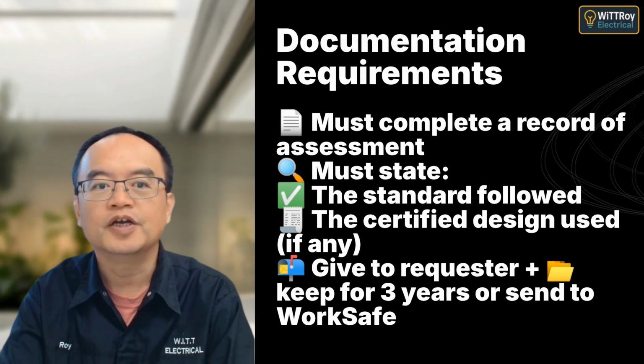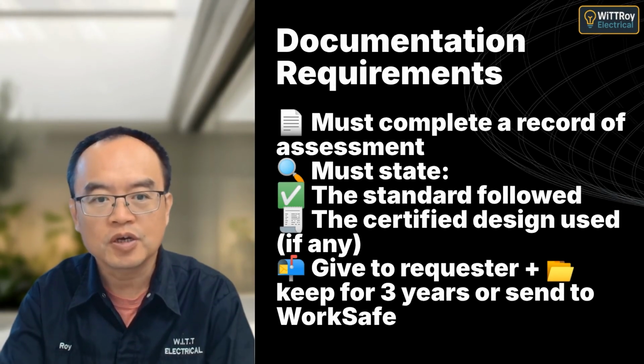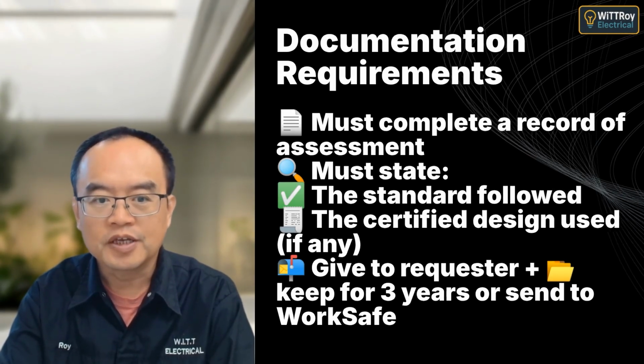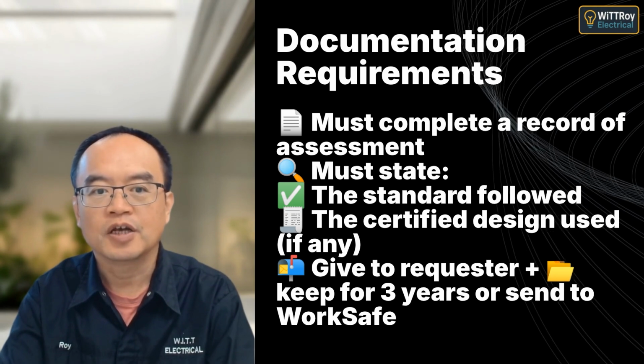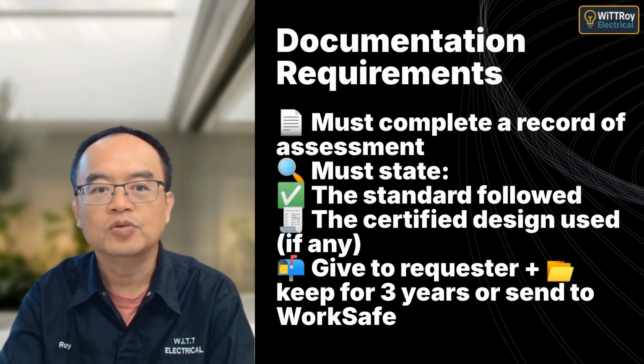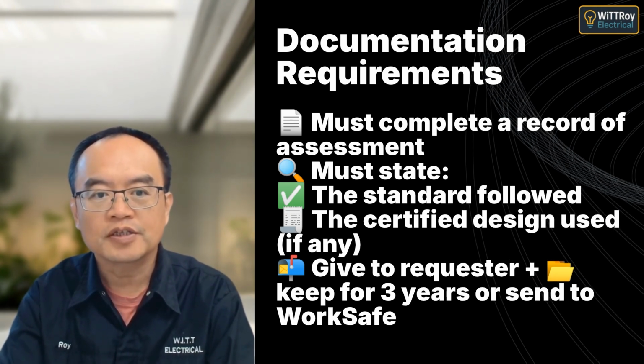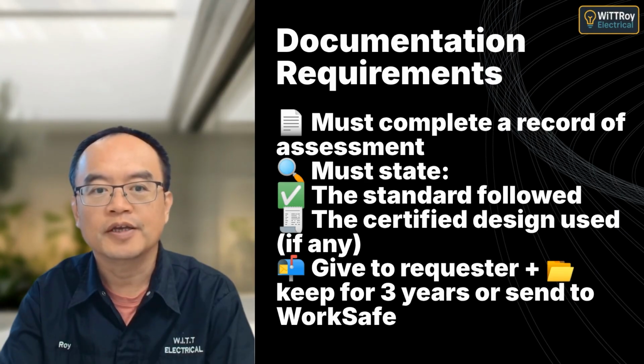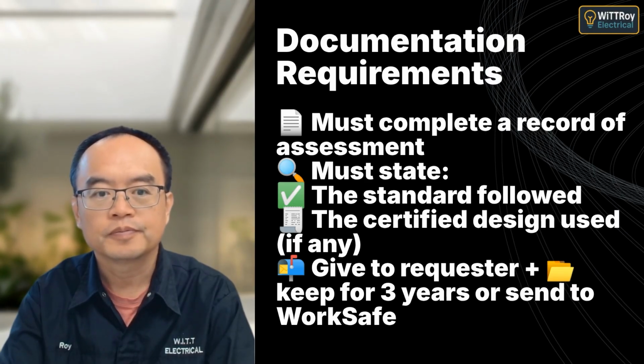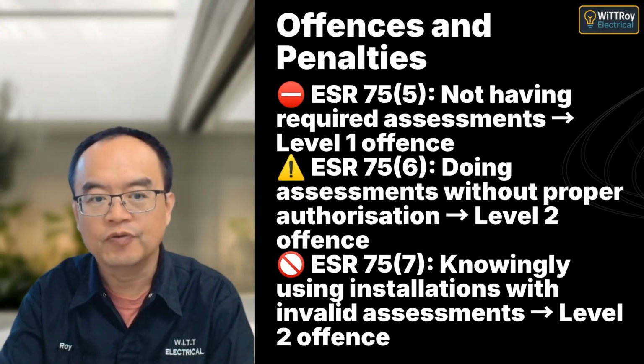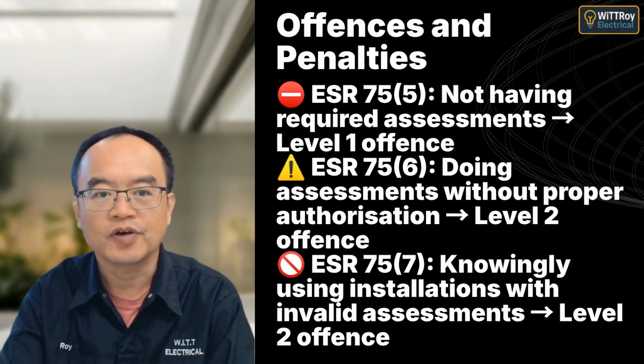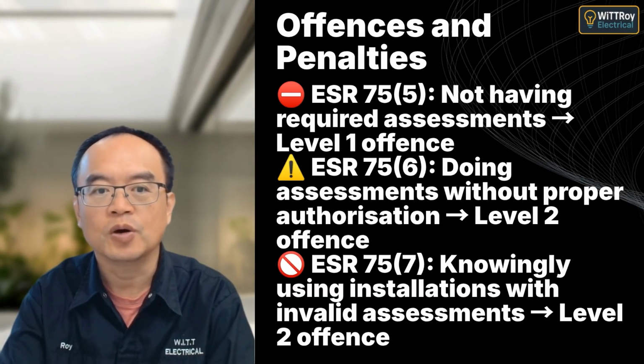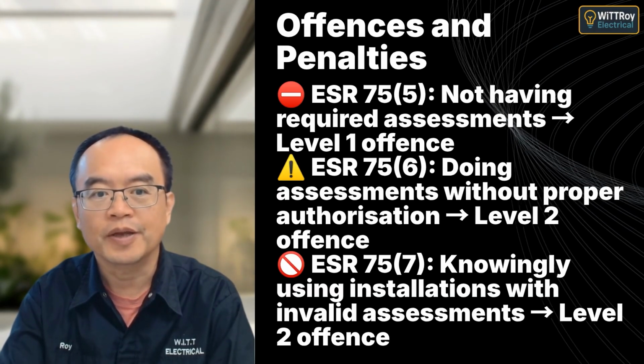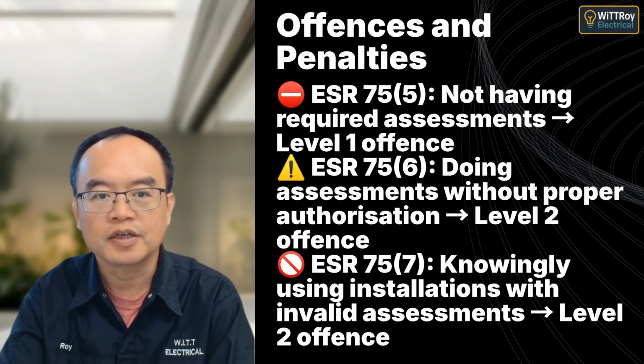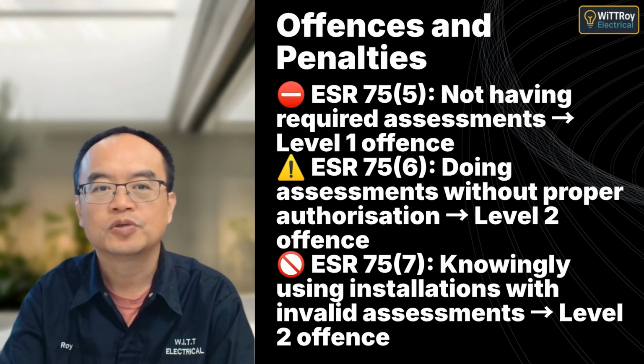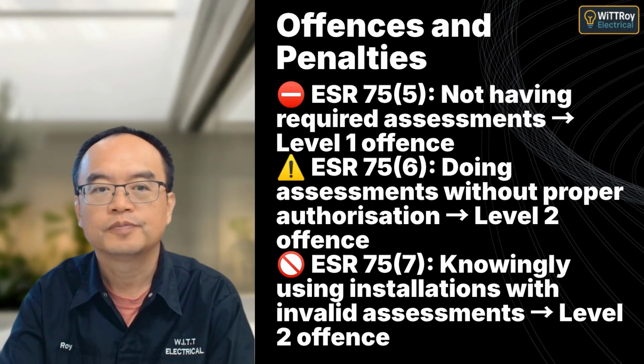Once the assessment is done, a record of assessment must be completed, not a certificate. The form must say what standard or certified design was used, and it must be given to the requester and stored for at least 3 years or sent to WorkSafe. Failing to follow the requirements of ESR 75 can result in level 1 or level 2 offences, depending on whether you're the owner, the assessor, or knowingly using a non-compliant installation.